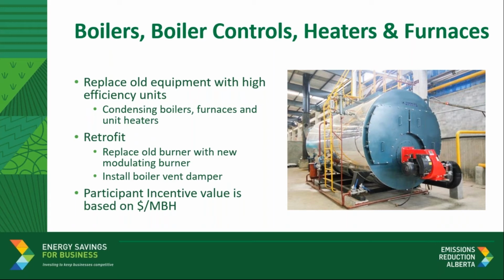However, what about these measures make them high efficiency? And is that relative to existing technology or available technology? Yes, condensing boilers or condensing unit heaters or high efficiency furnaces are common technology these days. They are specially designed to have additional heat exchange surfaces that can extract more heat from the flue gas, and therefore increase the thermal efficiency of the system. However, they come at a premium price because of the engineering and high grade materials. And that's why the Energy Savings for Business program is trying to encourage and support businesses to make these investments so they can go the extra mile.